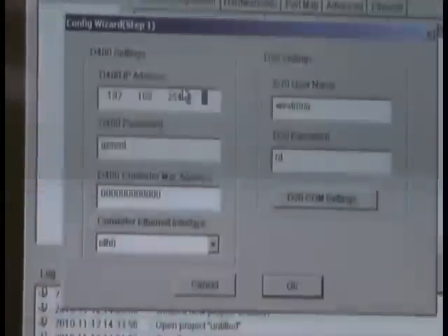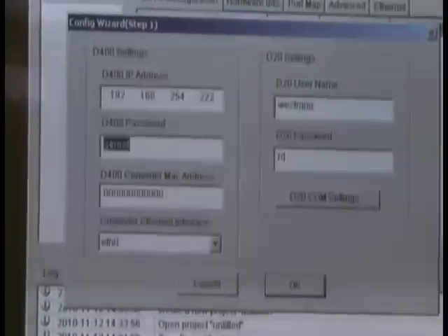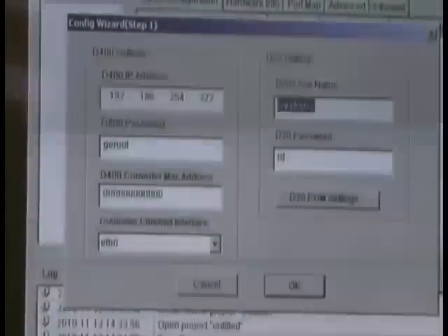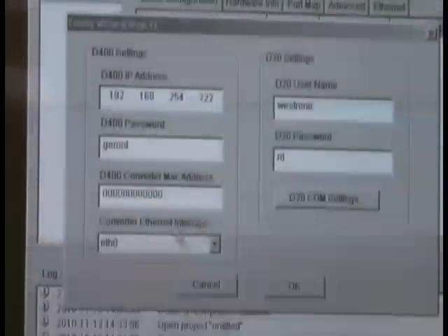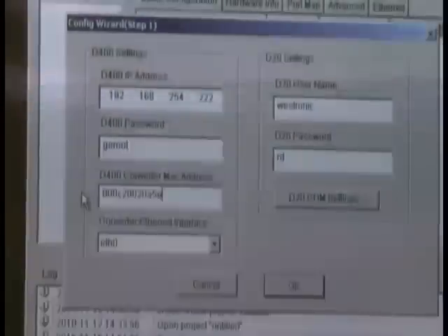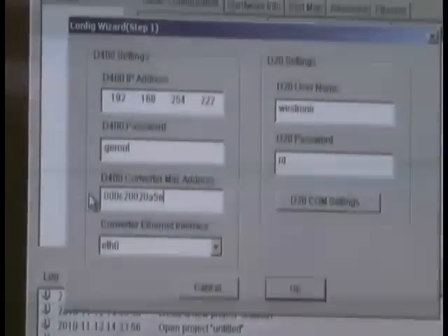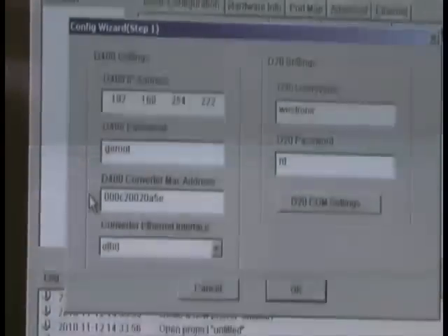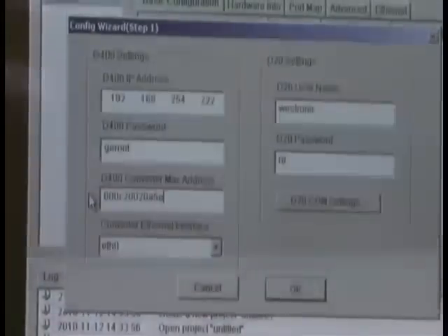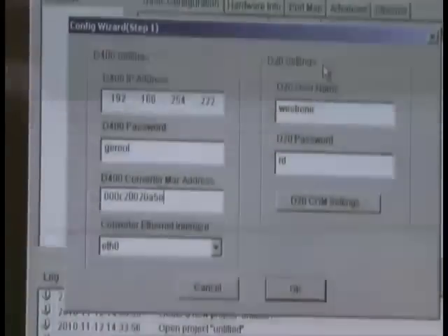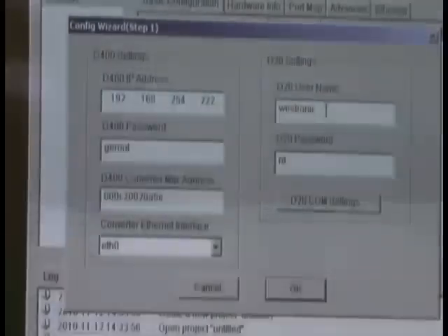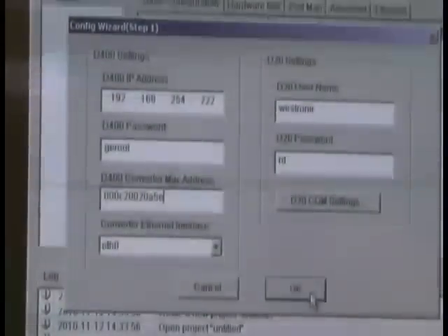So what we do on the D400 settings is put in the IP address of the D400, the D400 telnet password, and we punch in the MAC address of the Ethernet HDLC converter, and that MAC address is on a label on the back of each module that ships, so you just copy it down off of that.